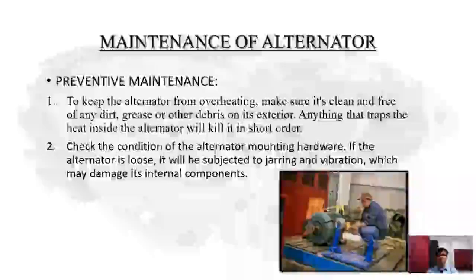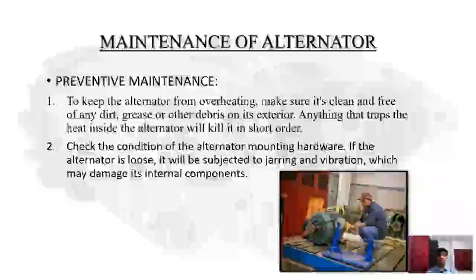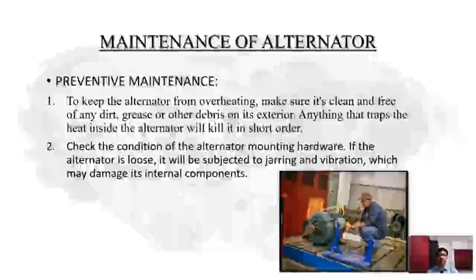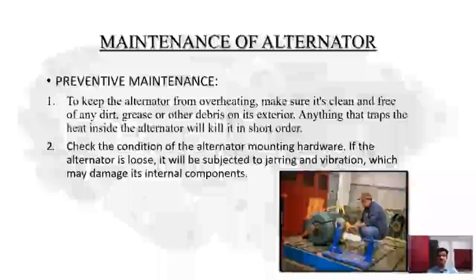In the next slide we can see the maintenance of alternator. Here what is preventive maintenance? The preventive maintenance tells us that to keep the alternator from overheating, make sure it is clean, free from any dirt, grease or other debris on its exterior. Anything that traps the heat inside the alternator will kill it in short order. Check the conditions of the alternator mounting hardware. If the alternator is loose it will be subjected to jarring and vibration which may damage its internal components. This is very dangerous for health of alternator.